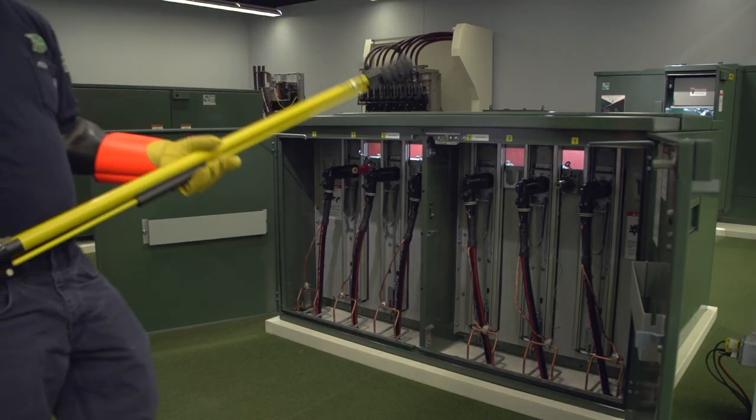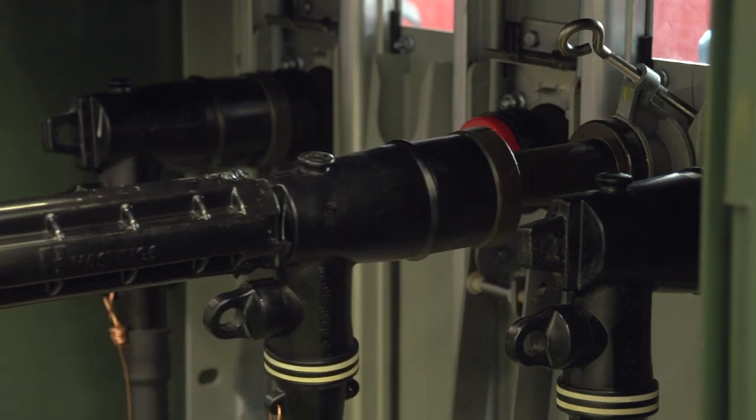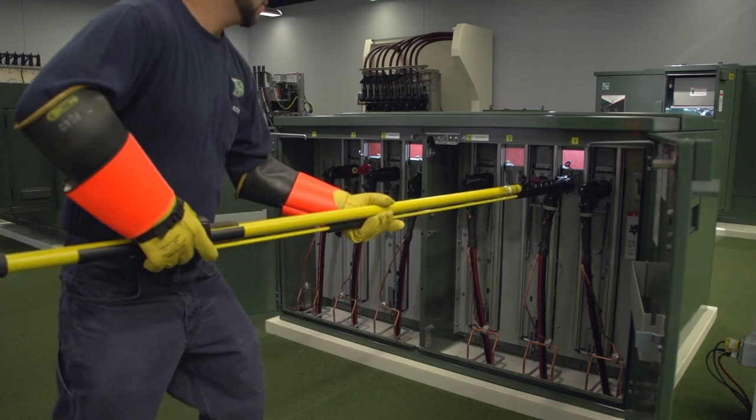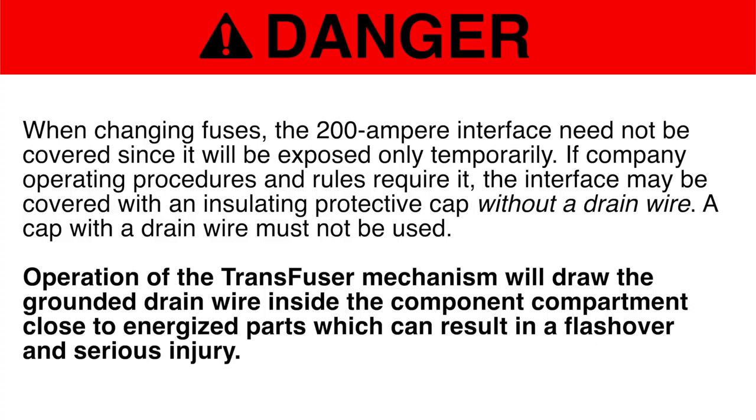Using the shotgun stick and following the elbow manufacturer's instructions for load break operation, remove the 200-ampere load break elbow, thus interrupting any load through the fuse to be removed, and move the elbow to the portable feed-through or stand-off insulator. Danger: When changing fuses, the 200-ampere interface need not be covered since it will be exposed only temporarily. If company operating procedures and rules require it, the interface may be covered with an insulating protective cap without a drain wire. A cap with a drain wire must not be used, as operation of the transfuser mechanism will draw the grounded drain wire inside the component compartment close to energized parts, which can result in a flashover and serious injury.